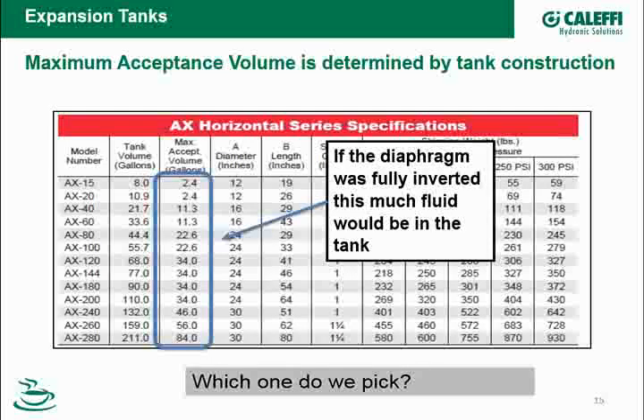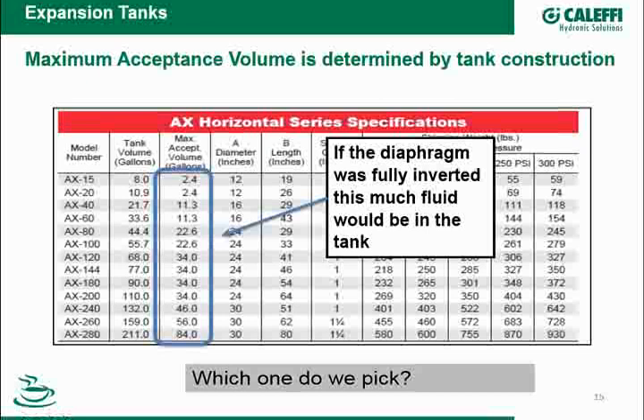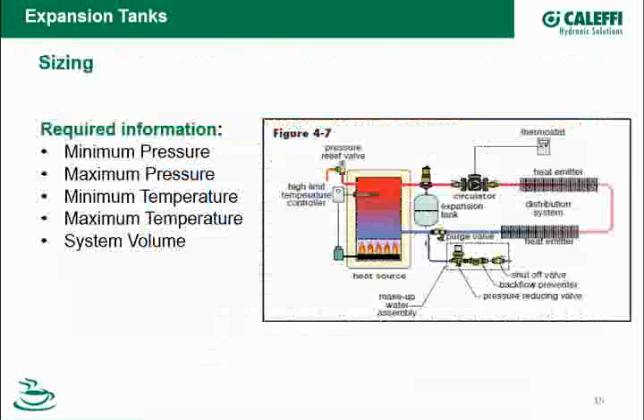So, if I do need to size the expansion tank, there are 5 pieces of information that I need. I need to know the minimum system pressure and the maximum system pressure. I need to know the minimum system temperature and the maximum system temperature. And then I need to know the system water volume. All of these play a part in selecting the right size expansion tank.